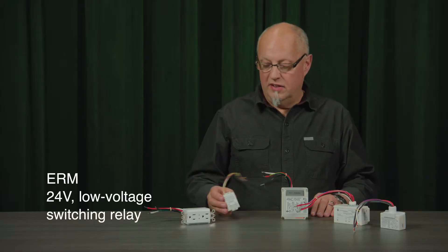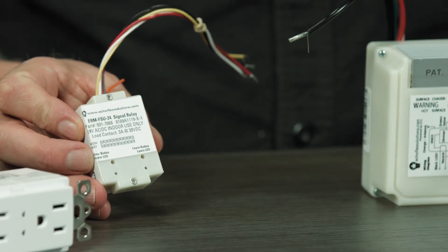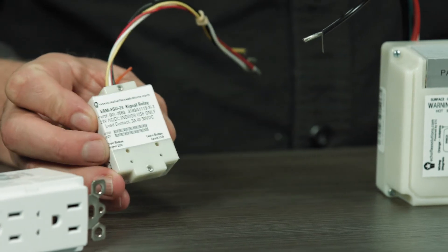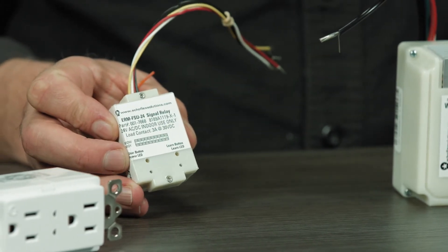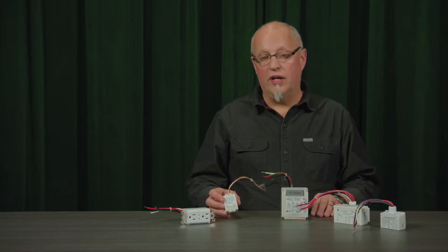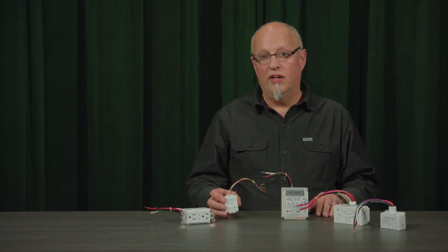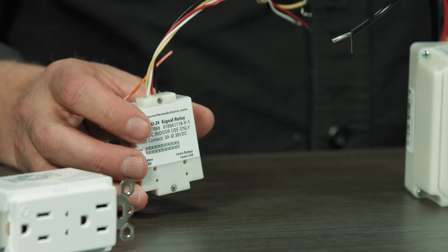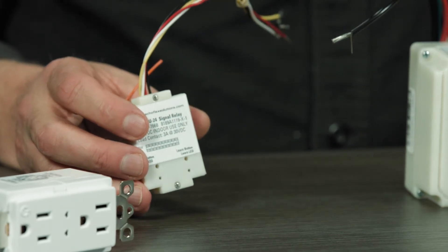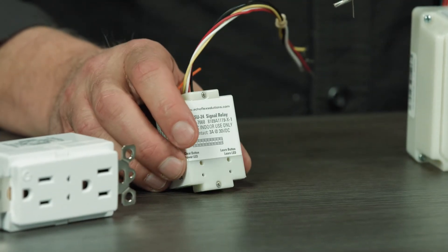Moving over to my right, this is a low voltage version of our switching relay, the ERM model. And this is the 24 volt version. It also comes as a 120 through 277 volt version. It has a dry contact output and is excellent for HVAC integration applications, where you want to be able to take your lighting occupancy sensors, your wireless sensors, and link them into your HVAC system. This device will be powered off of the 24 volt from the HVAC controller and the dry contact can be wired in to one of the inputs for occupancy state for the HVAC controllers.